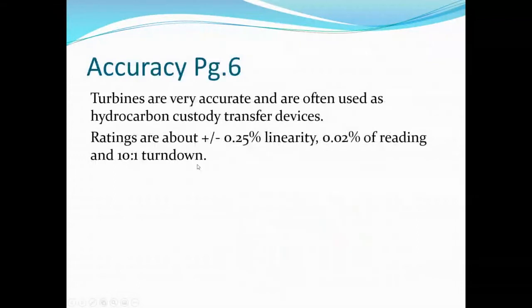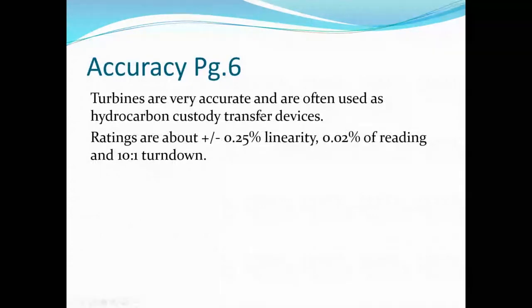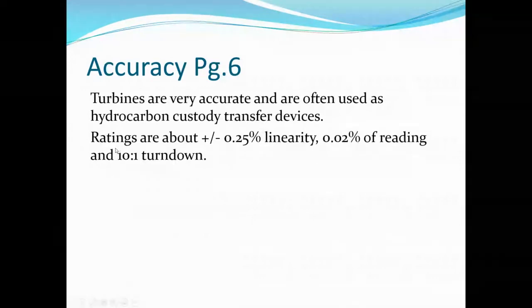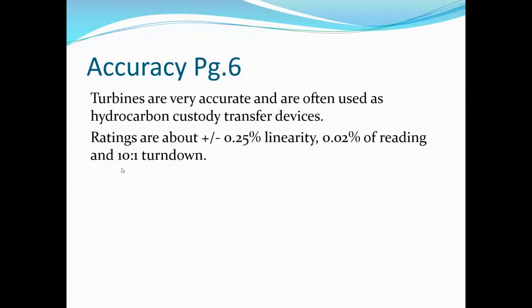Accuracy for turbine meters is very good — often used in hydrocarbon custody transfer. Ratings are about plus or minus 0.25% on linearity, 0.02% of reading for accuracy, and a 10-to-1 turndown ratio. Turndown indicates how accurately the meter measures throughout a wide operating range. For example, a 1,000 liter per minute turbine meter with 10-to-1 turndown would be equally accurate at 1,000 liters and at 100 liters per minute.